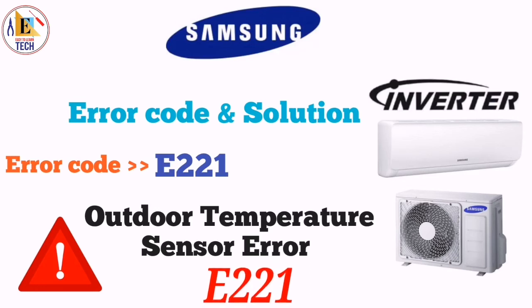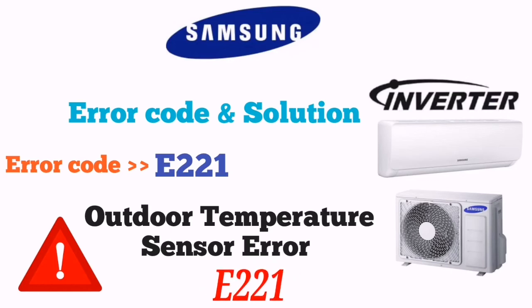If the error has not gone, then you have to check that sensor connector A is connected correctly according to the color. If it is connected correctly, then you have to check the resistance of sensor B. It should be 10 kilo ohms plus minus 3% at a room temperature of 23 degrees Celsius. After that, remove the connector from your PCB and check the supply voltage of the connector. It should be between 0.5 V DC and 4.5 V DC. If it doesn't give the same voltage, it means a micom error. Then you have to change the outdoor PCB and it will work.